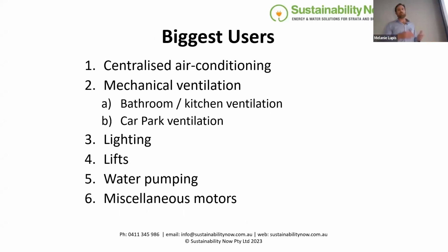So the biggest users of energy, like I said, centralized air - if you've got a chiller system or a condenser water plant, that sort of thing, they're always going to use the most. Other mechanical ventilation, like bathroom and kitchen exhausts, the Australian standard 1668.2 says they need to run 24/7 unless you can monitor occupancy in those spaces. Some newer buildings have the ventilation systems hooked up to the lighting circuit - if everyone in that stack has their bathroom light turned off, it'll shut down their ventilation fans, but as soon as one person turns it on, it comes on again. That's a kind of newish innovation. Then there's lighting, lifts, pumping water around the place, and just miscellaneous motors and that sort of thing.